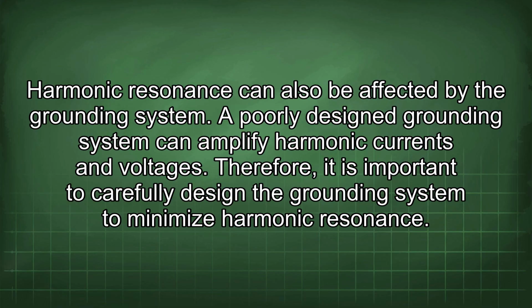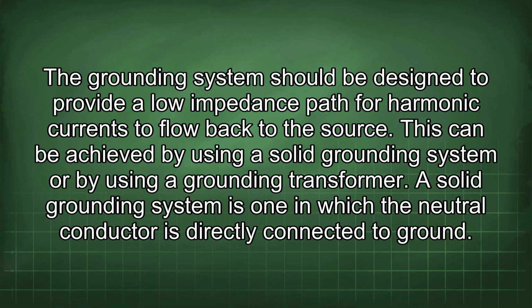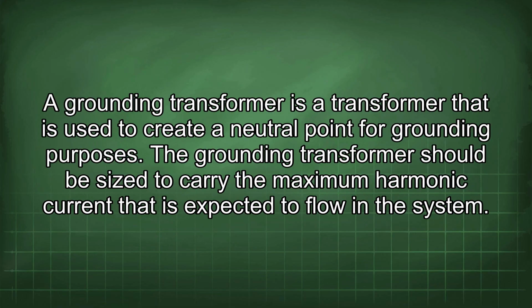A poorly designed grounding system can amplify harmonic currents and voltages. Therefore, it is important to carefully design the grounding system to minimize harmonic resonance. The grounding system should be designed to provide a low impedance path for harmonic currents to flow back to the source. This can be achieved by using a solid grounding system or by using a grounding transformer. A solid grounding system is one in which the neutral conductor is directly connected to ground. A grounding transformer is a transformer that is used to create a neutral point for grounding purposes.